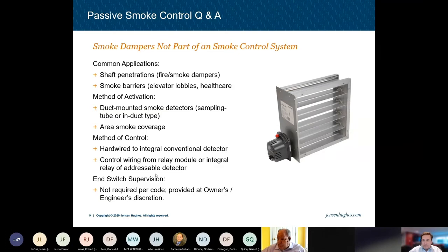So I think before we dive into this, there was a request to talk about smoke dampers. Smoke dampers are not part, or sometimes they are part of the smoke control system, but when they're not provided as part of a smoke control system, some common applications are shaft penetrations and smoke barriers. So you'll have fire smoke dampers at shaft penetrations. And then smoke barriers, elevator lobbies, healthcare.